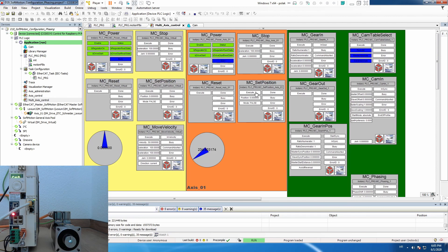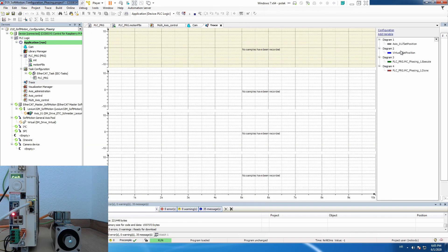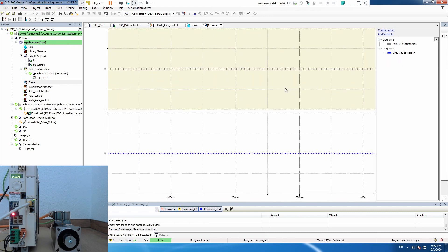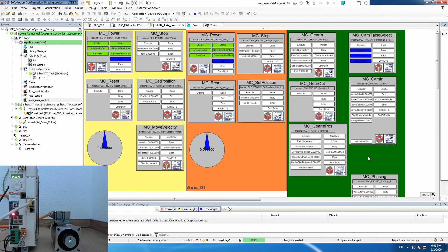We can now enable our drives. We need to put the slave to 0, so let's execute MC Set Position. You can also see that on MC Cam Table Select we set periodic — that means when the period is finished it will start again. For that we will also use trace, using the two set positions of our master and slave axis, and delete the rest. Let's download our trace. First you need to execute MC Cam Table Select to select the cam table. When it's done, you can run your MC Cam In. And immediately it's in sync because it's at the 0, 0 position.